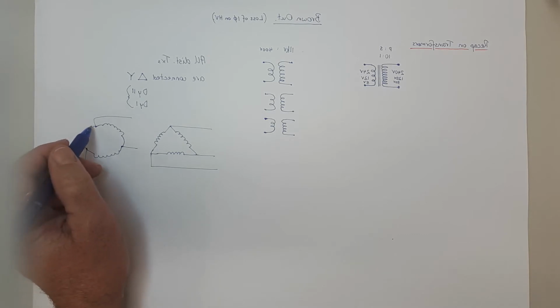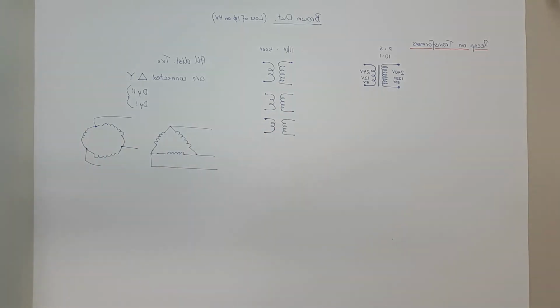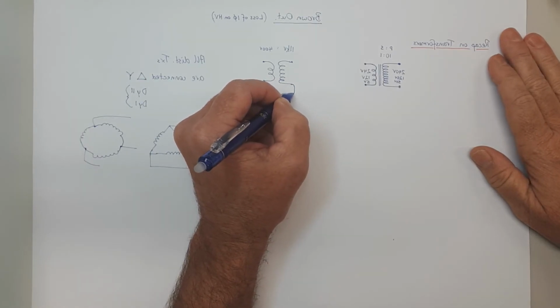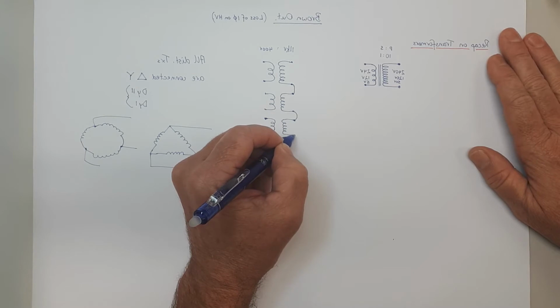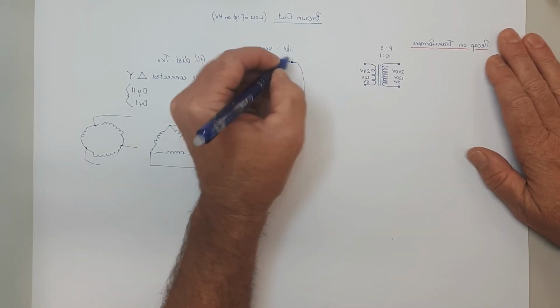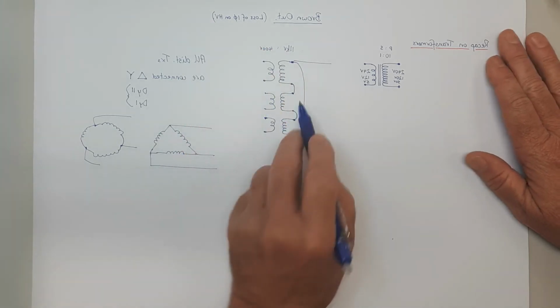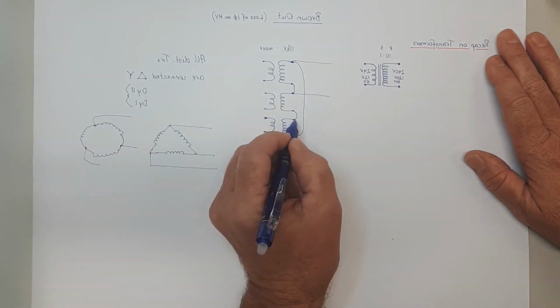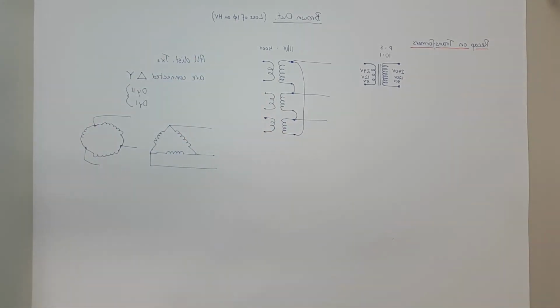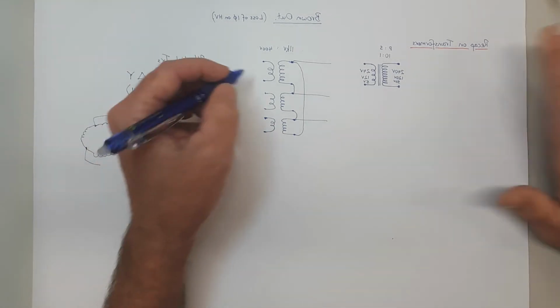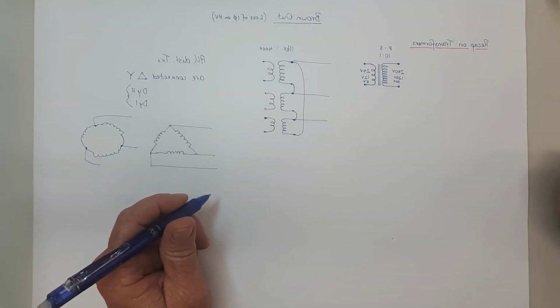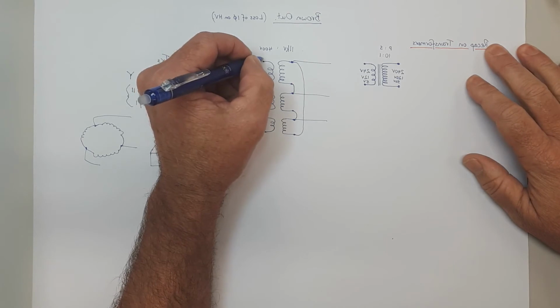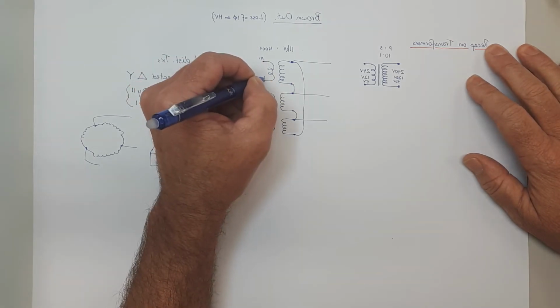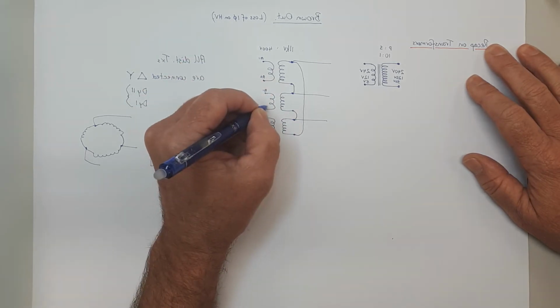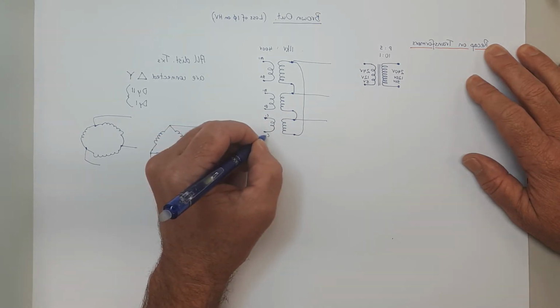And so the key point is we could connect it as a ring, and so that's what happens in the internals of the transformer. It's connected in a circle, right? So that circles back to there, and we bring in our phases like this. This is where you get your 3. Bring it in on the same side of each winding. So in this drawing, it's on the top side of each winding, and then of course the secondary is connected in star, as you know, and always you connect to the same side. So that might be A phase 1, that might be 2, that'll be B1, B2, and that'll be C1 and C2. So we star up all the 2s.